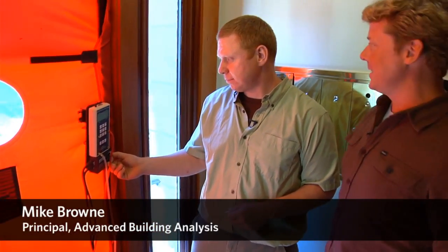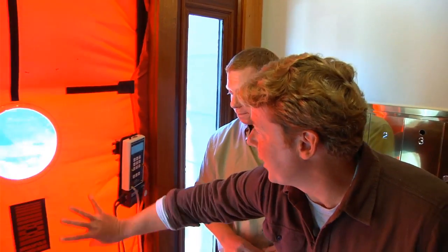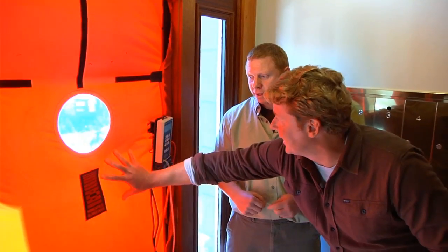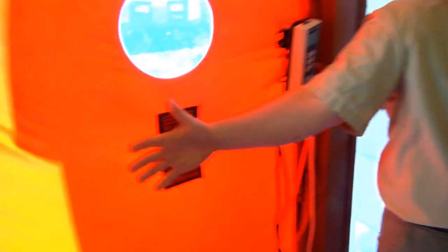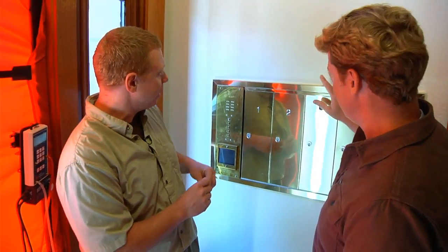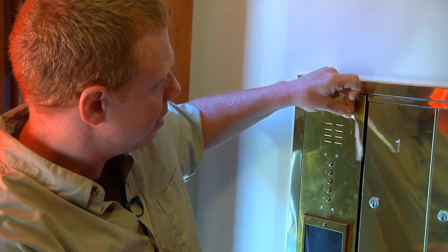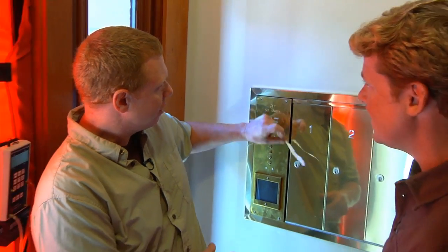Mike, you're helping us plug up this house and stop all the leaks? Yeah, we're running the blower door now. And this is doing what for us? We're sucking air out of the house. We're finding out where it comes in. So by sucking the air out, air wants to get back in. And this is actually the pressure on the outside trying to get in here, and that's happening all throughout this building — the ceiling, all the walls, even the foundation. If we go around the house, we can find any leaks. There are still a few remaining, and we can illustrate one right here. You can see how that blows out. So by illustrating them with a fan, we can go around and find them and eliminate them. That's what we've done before sheetrock went into this building. You actually tightened this building up considerably? Yeah, probably by more than half since we first started measuring it.